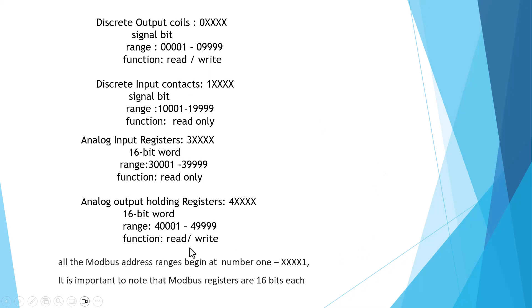To summarize: all Modbus address ranges begin at number one — the first address is always one. These are all absolute addresses. The ranges are 00001–09999, 10001–19999, 30001–39999, and 40001–49999. All Modbus blocks use 16 bits, but in discrete output and discrete input only one bit is used, and the other 15 bits are wasted. Only the input and holding registers use the full 16-bit word.